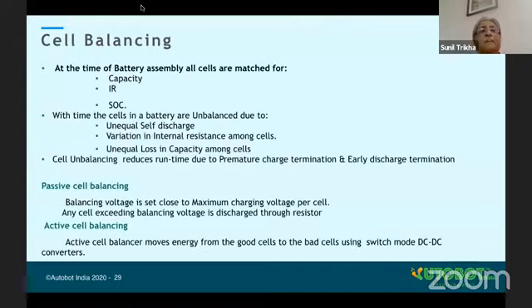Now I'm just giving a little idea - balancing itself can be done by two methods. One is called passive balancing. Passive balancing is when battery is fully charged, after the battery is fully charged, it just monitors each and every cell voltage, and wherever voltage is higher than a threshold, it discharges them and brings it to a lower value, to the threshold value, so that all the cells are at the same level. This occurs only by discharging through a resistor, one cell at a time, and it happens only when the battery is fully charged.